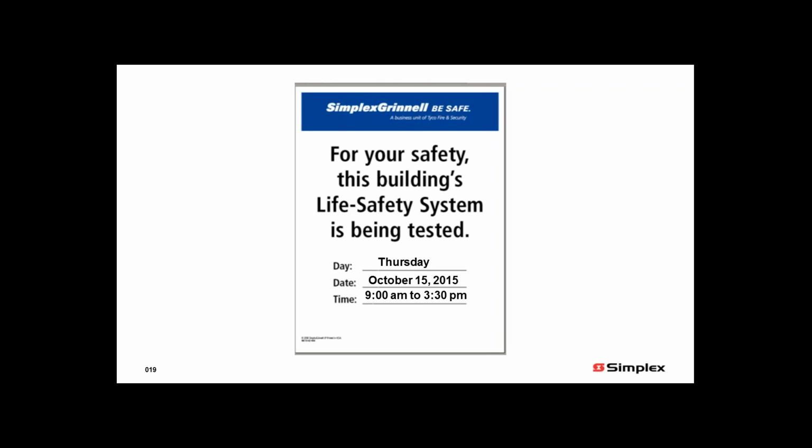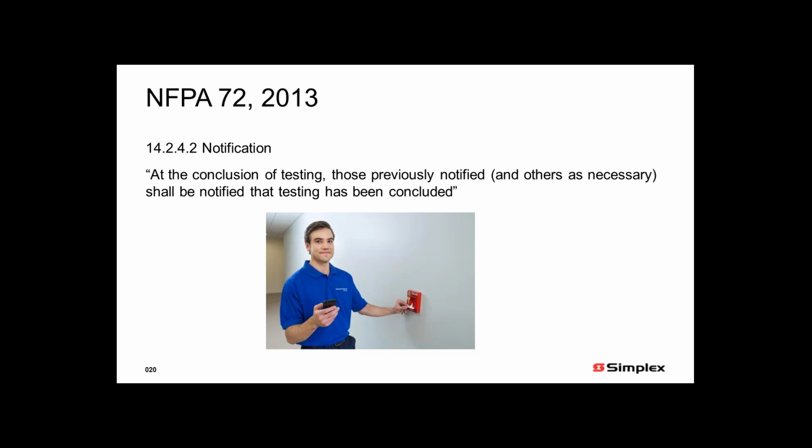And a lot of people do this. They'll put notes under the doors or tape things to the windows. But this was one part that we don't see people doing a lot. It's in 14.2.4.2. And we say at the conclusion of the testing, those that were previously notified shall be notified that testing has been concluded.